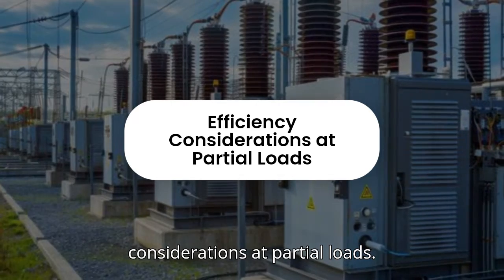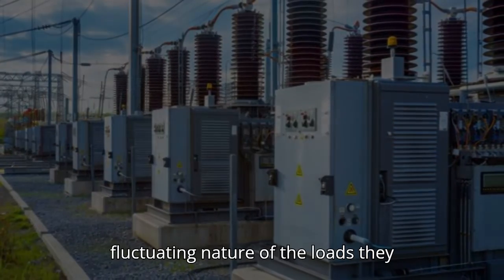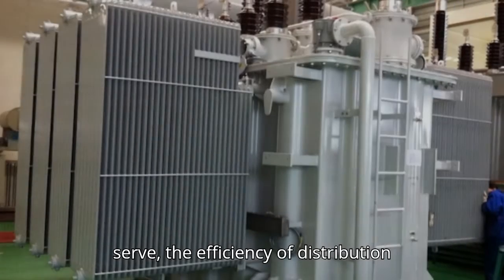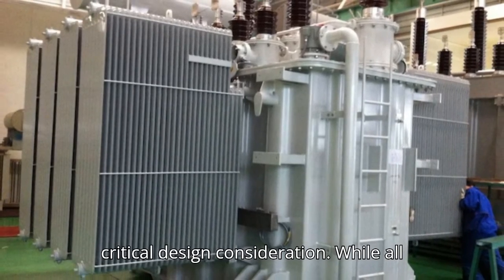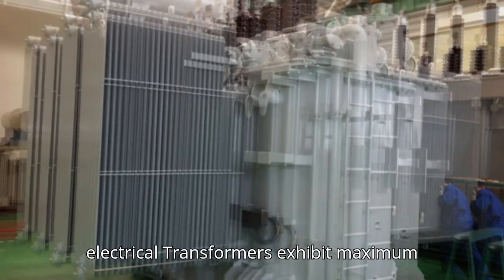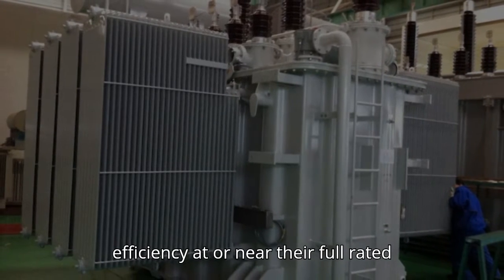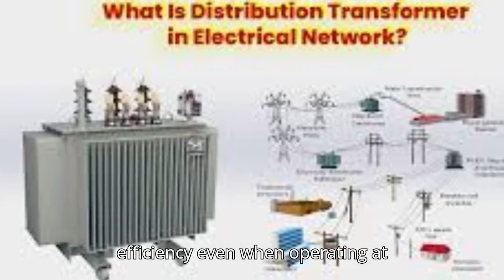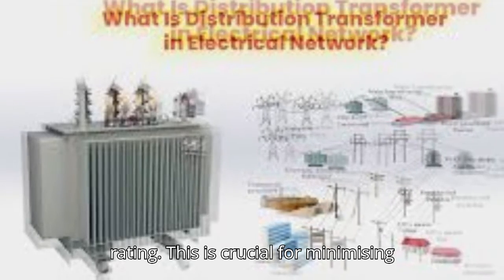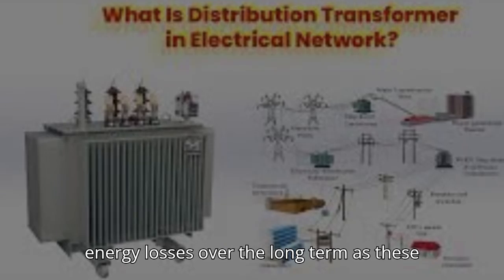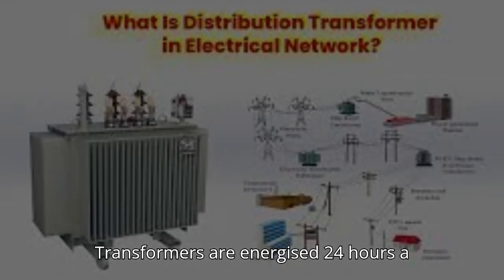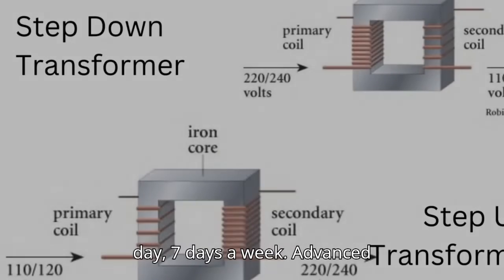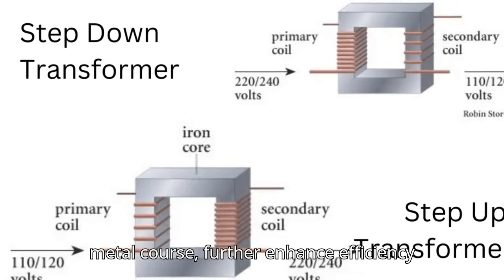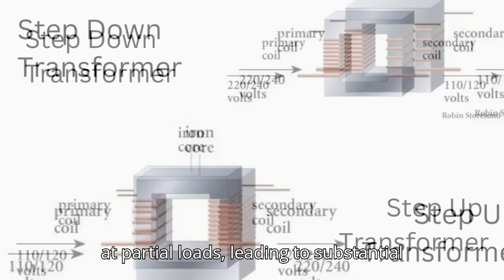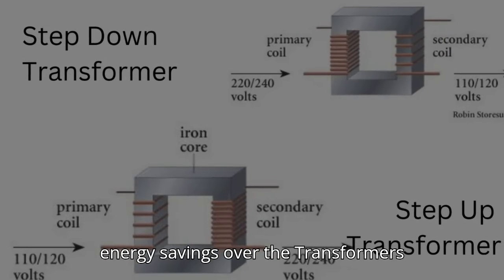Efficiency considerations at partial loads. Given their continuous operation and the fluctuating nature of the loads they serve, the efficiency of distribution transformers at partial loads is a critical design consideration. While all electrical transformers exhibit maximum efficiency at or near their full rated capacity, distribution transformers are specifically engineered to maintain high efficiency even when operating at significantly less than their maximum kVA rating. This is crucial for minimizing energy losses over the long term, as these transformers are energized 24 hours a day, 7 days a week. Advanced designs, including those with amorphous metal cores, further enhance efficiency at partial loads, leading to substantial energy savings over the transformer's lifespan.